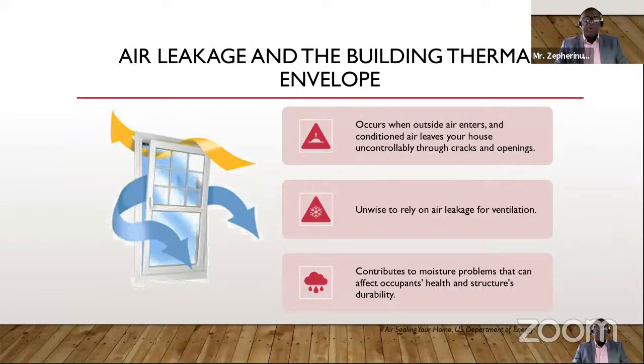Now, air leakage and the building envelope, the building thermal envelope, air leakage occurs when outside air enters and conditioned air leaves your house uncontrollably through cracks and openings. This is a very common thing in our region. As a matter of fact, most of our buildings, what appears to be the norm is that the buildings are ventilated because of air leakage. And ventilation should be intentional, not through leakage. It's unwise to rely on air leakage for ventilation, and it contributes to moisture problems that can affect occupants' health and structures' durability. So a tight envelope, if you're utilizing the code for your residential building, the code promotes having a very tight envelope, and ventilation would be by design, intentional.